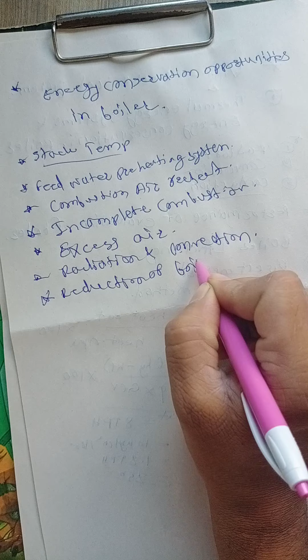Next, reduction of boiler steam pressure. This is an effective means of reducing fuel consumption, if permissible, by as much as 1 to 2%. Lower steam pressure gives a lower saturated steam temperature, and without stack heat recovery, a similar reduction in the flue gas temperature results.